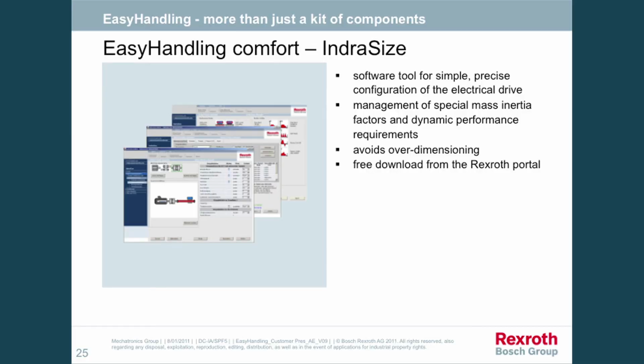At the comfort level, we have software called IndraSize, available online and downloadable, that lets you size the motor and drive combination. You can do it yourself, but we also work with you on these applications when needed. It takes into account mass inertia, and it's so important to stress that it avoids over-dimensioning -- it's about right-sizing, which we touched on earlier. Very, very critical in doing that.